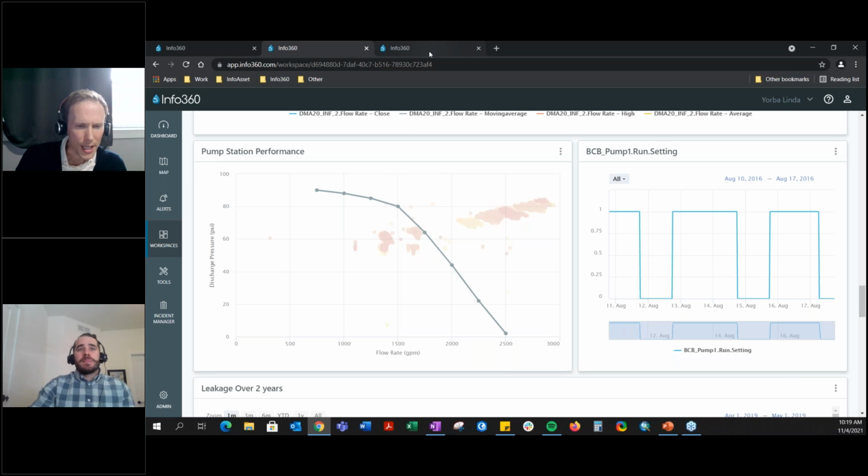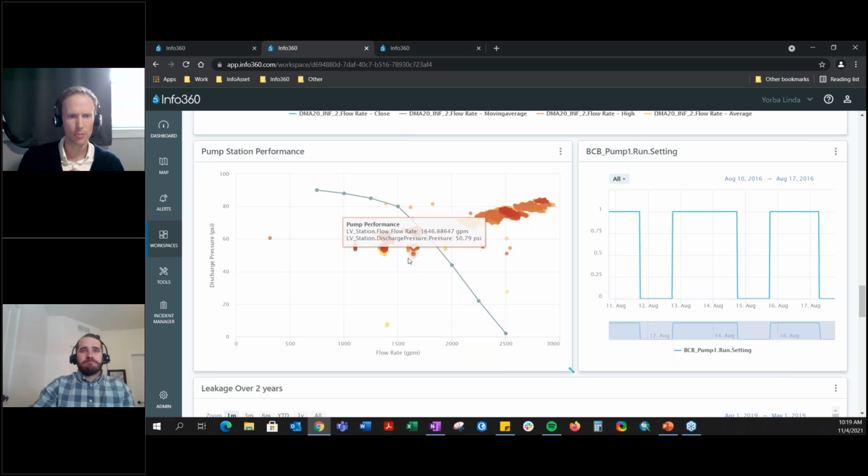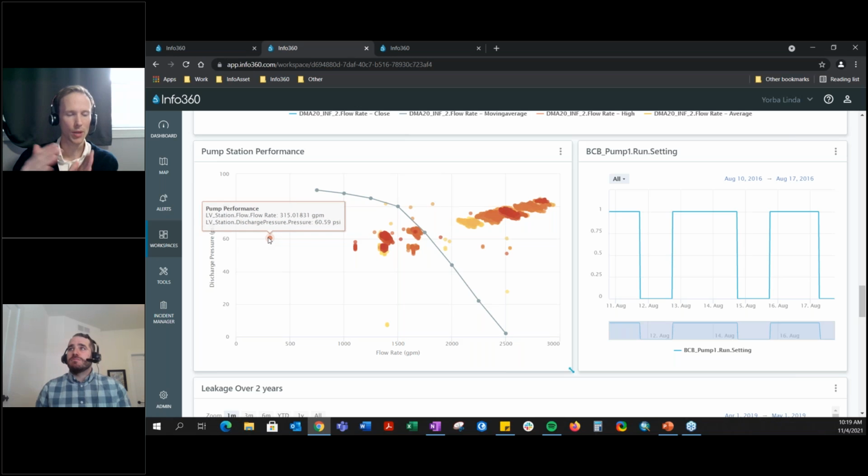Yeah, that graph is kind of graying out now, but that one shows a few thousand data points, and it applies a color ramp according to time. So if you applied that to one pump, one time, you'd be able to see a color ramp of if there is any drift in the pump performance against the curve. Just some interesting tools. Yeah, definitely. And with the improved dashlets and how they're viewed and some of those added features, it's been really exciting to see where this has gone and where it can go as it visually continues to improve.